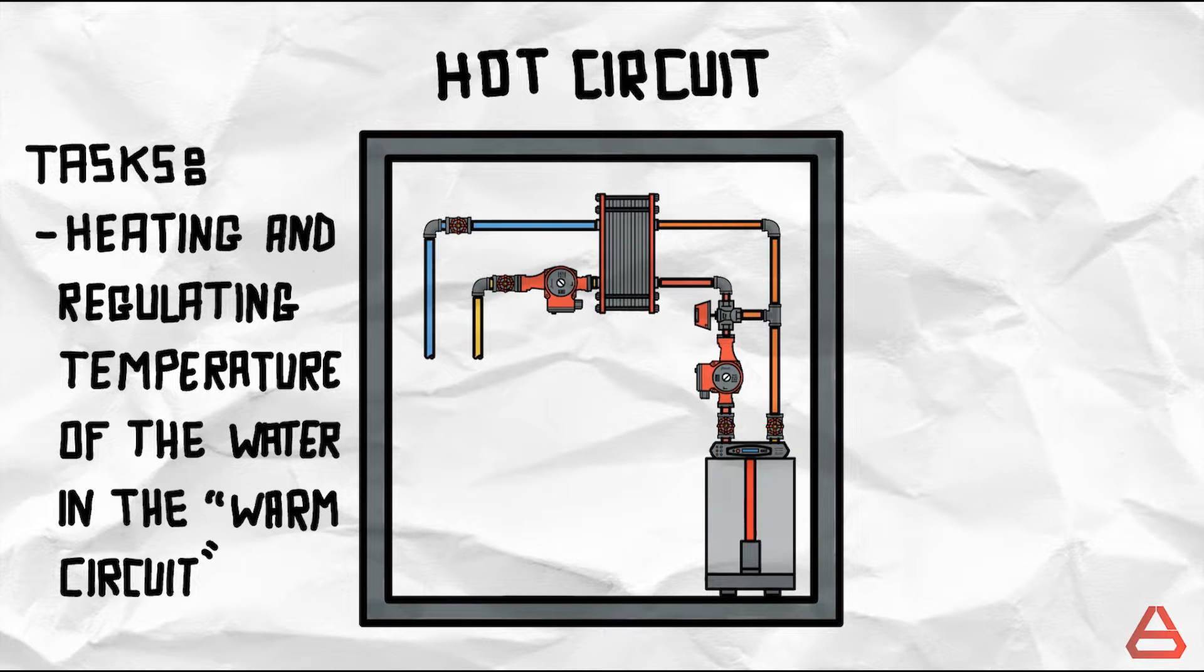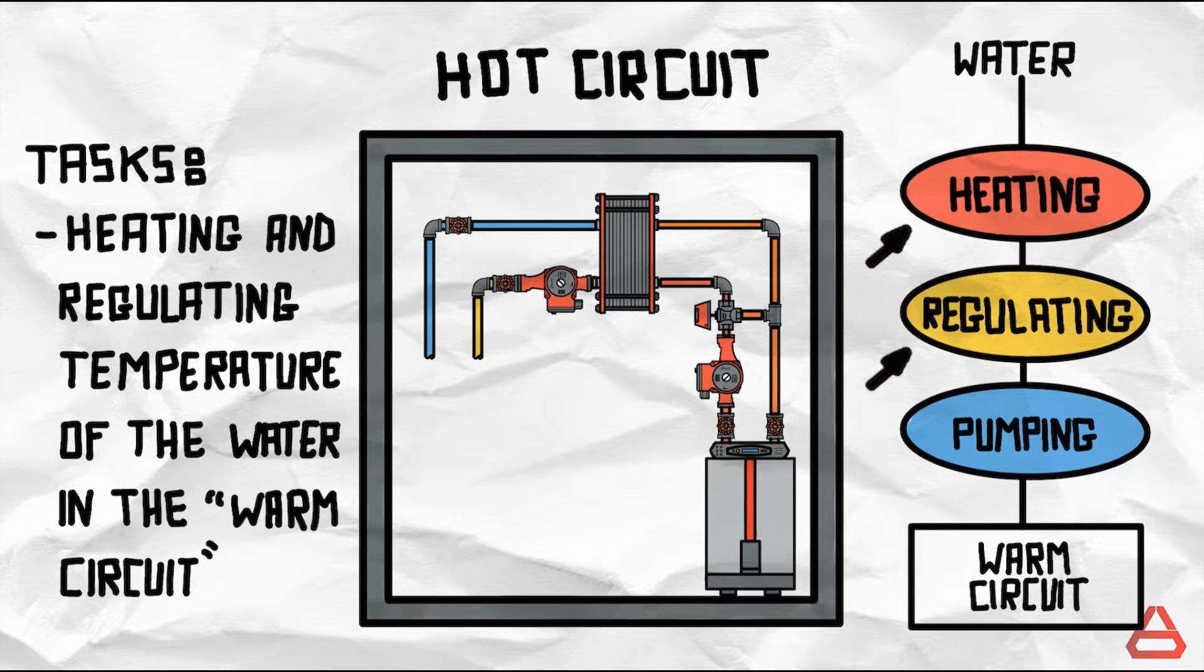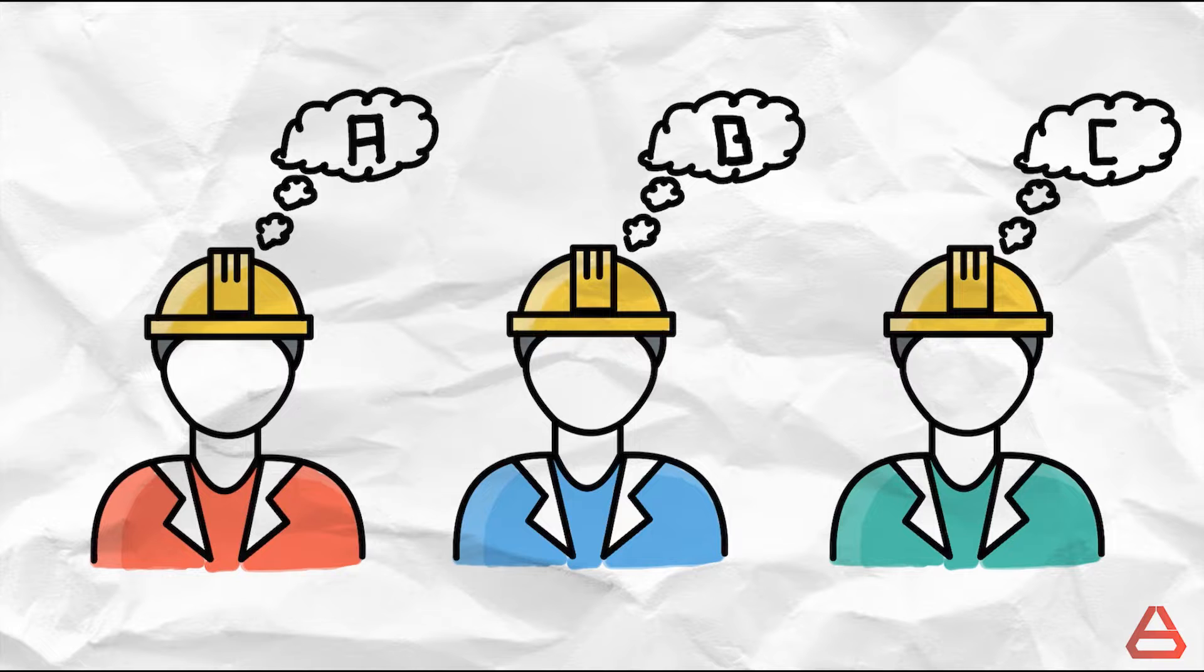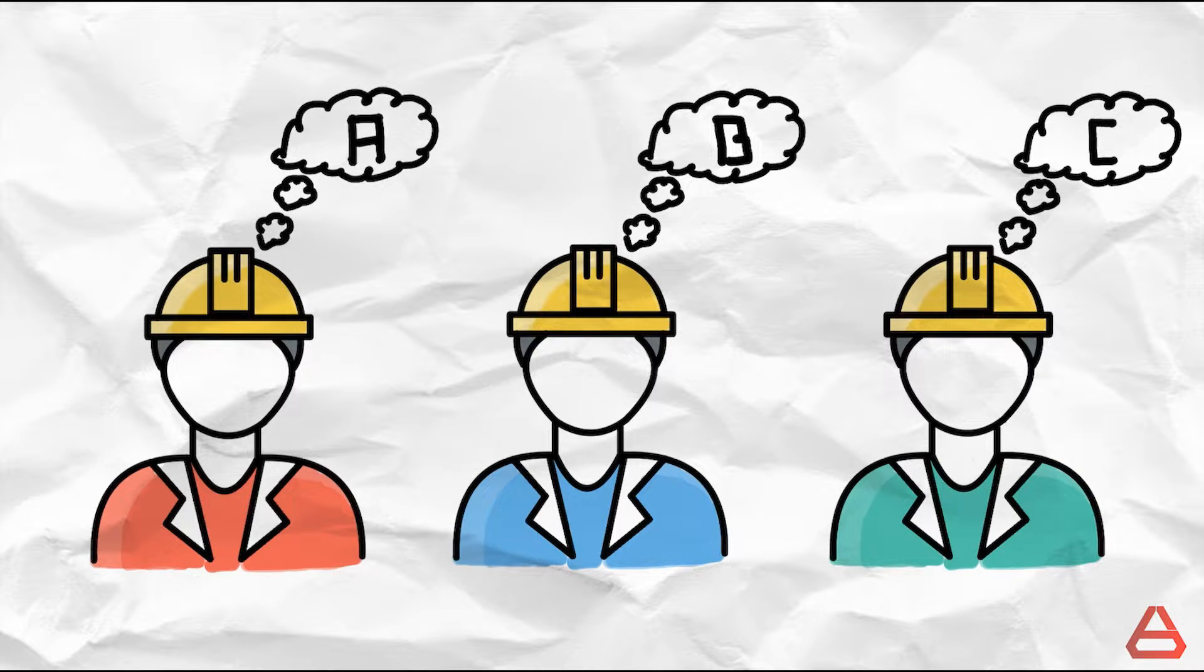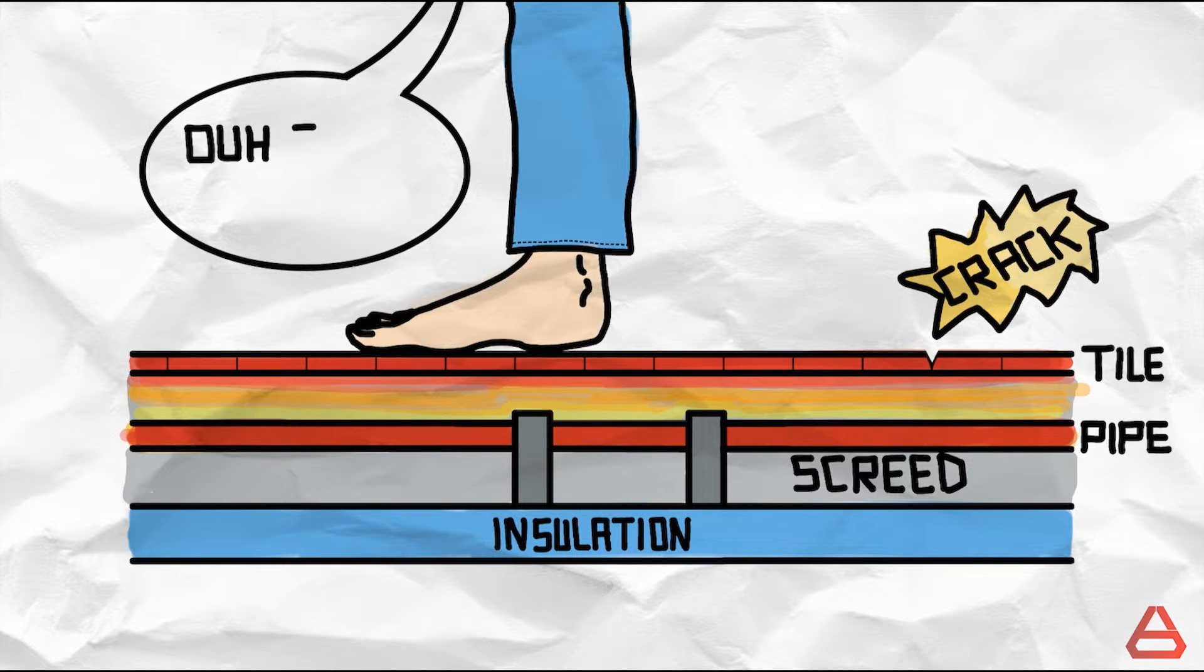Now let's move on to the second part which I refer to as the hot circuit. It is actually what heats, regulates and pumps the water in the warm circuit. It can vary between different designers depending on the situation and the preference of the designer. This circuit is present because having high temperature water in the warm circuit will cause damage to the flooring and discomfort, things which we don't want.